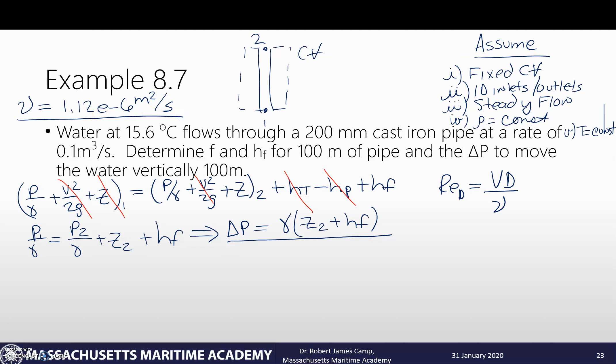Now we also need to calculate out velocity because we have diameter. Look at that velocity. That's not a velocity. That is a volumetric flow rate. So we need to make sure that we convert that over to our velocity. So what is velocity? Velocity is Q divided by A. Or Q, 0.1 cubic meters per second. Now I need to divide that. And this one's interesting because we usually do with the GPM. Cubic meters per second is already in base units. So we're good to go. Divide that by pi over 4. And then I have a 200 millimeter pipe, which is 0.2 meters squared. And when I calculate that out, I will get a velocity of 3.18 meters per second.